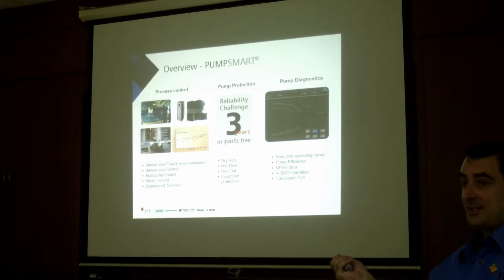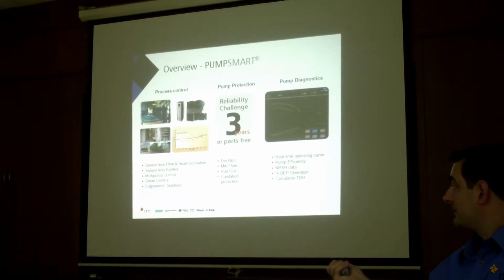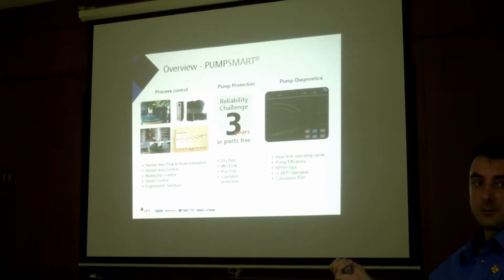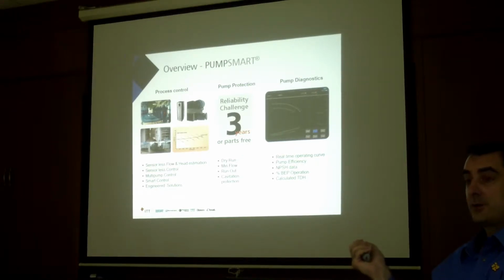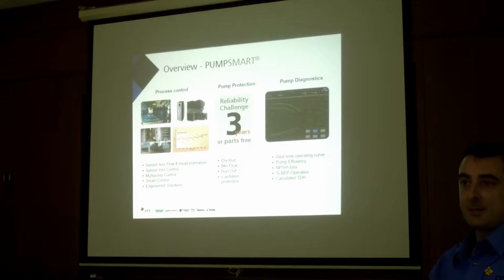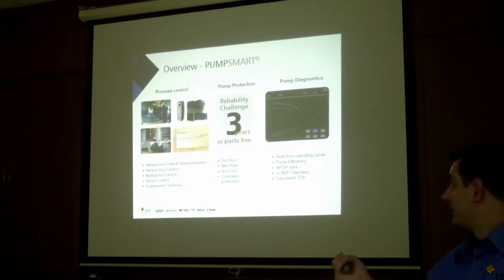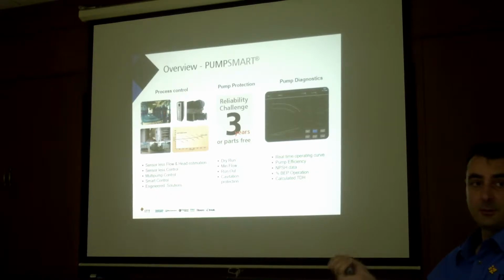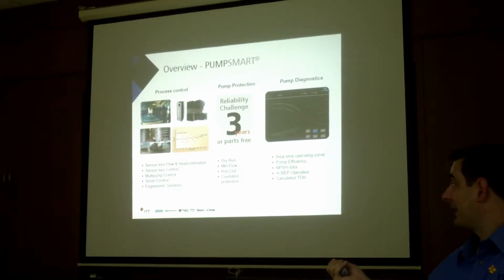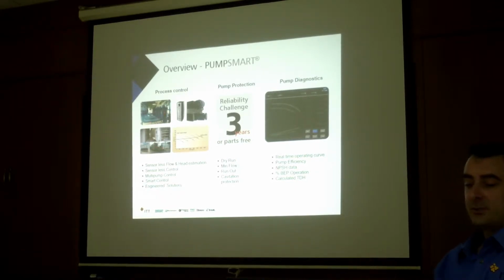So obviously, these are all the things that we do different to a normal variable speed drive. The big one is the sensorless flow. So we calculate the flow without the flow meter. So again, maybe we can save the customer money on that, on the flow meter, especially if it's a big pipeline. The other alternative is sometimes the products are all very different. So we can handle that too.